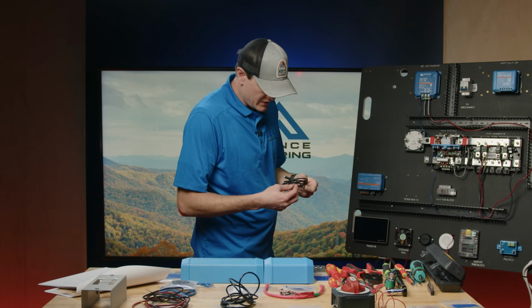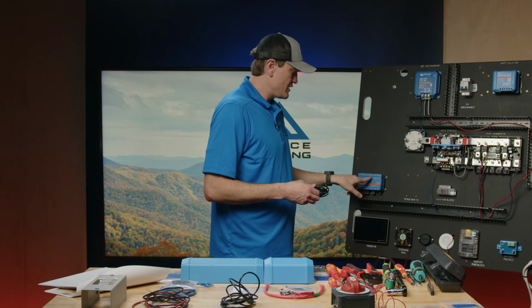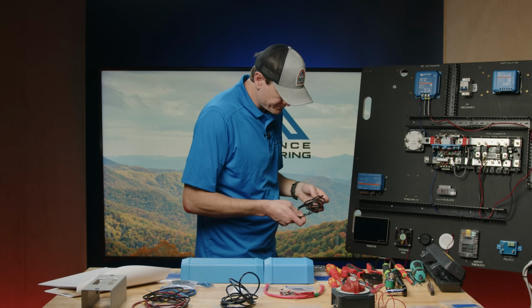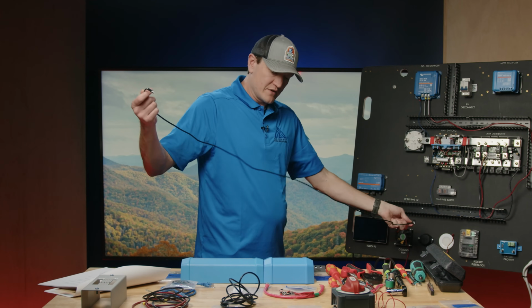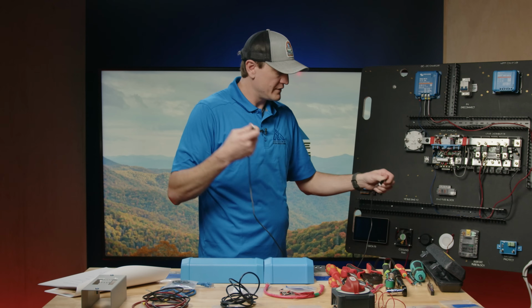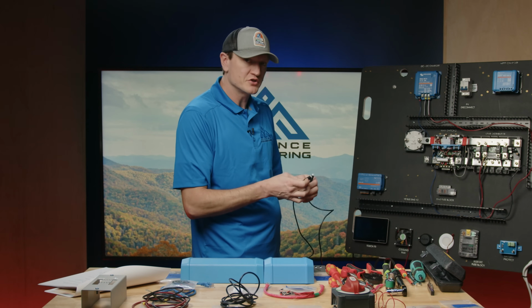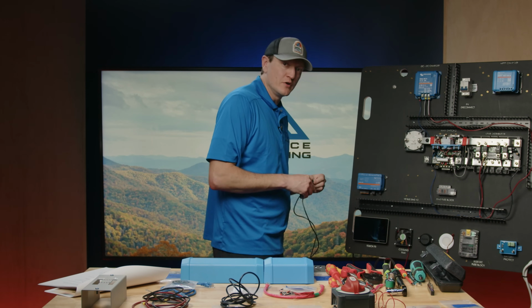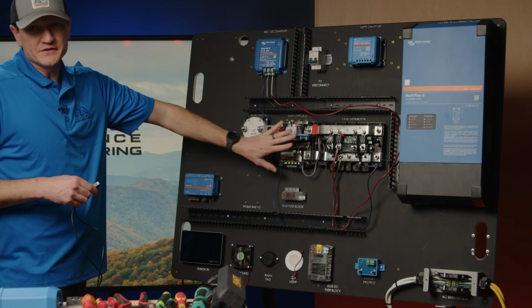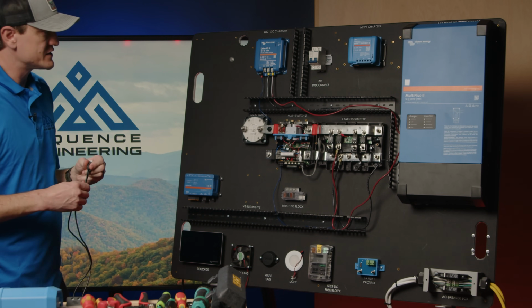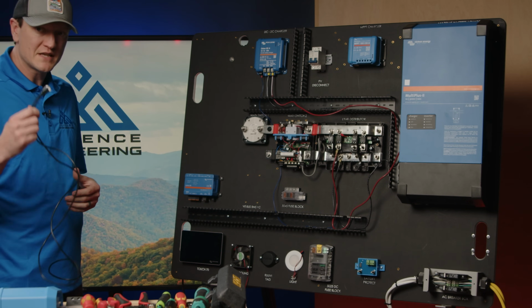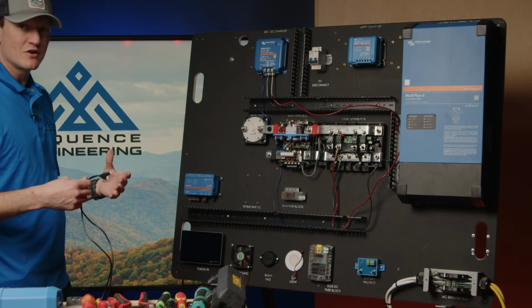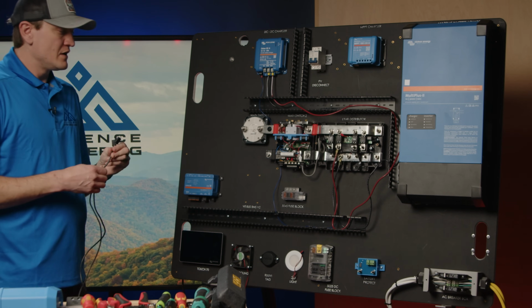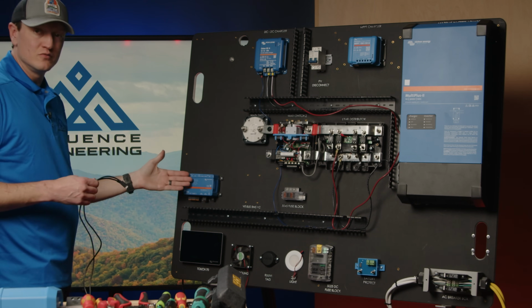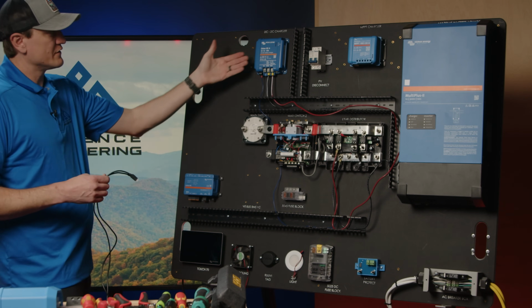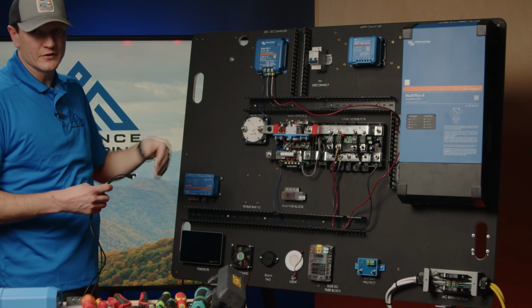We're going to connect a VE direct cable from here to the VE direct port on top of our Cerbo. When this cable is connected and a BMS is also connected to your Cerbo, it's smart enough to know the BMS is in control of everything else in the system. So if you have a device without a remote port but with a VE direct port, and you're using a Victron BMS, the BMS tells the Cerbo what's happening, and the Cerbo tells this device when to operate and when not to operate.